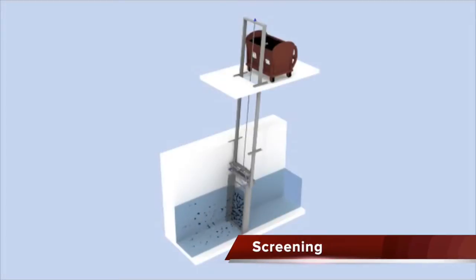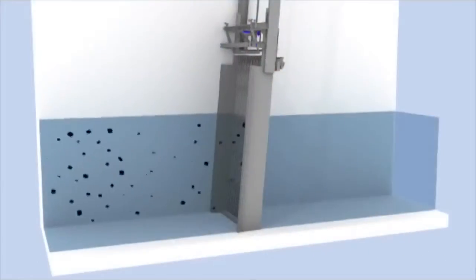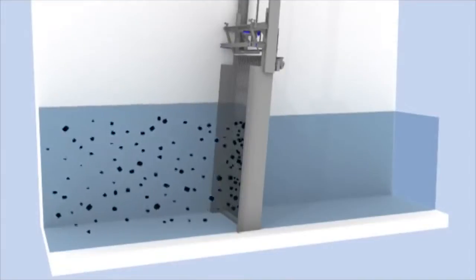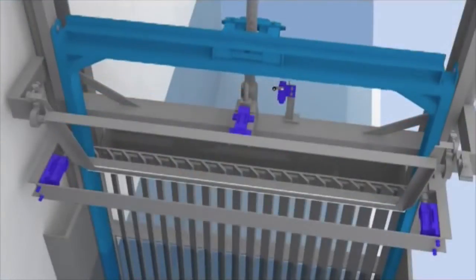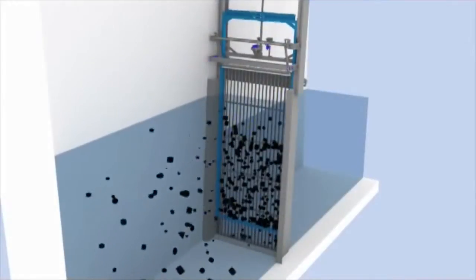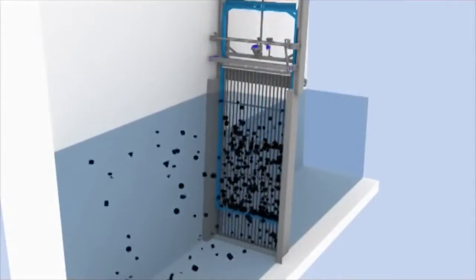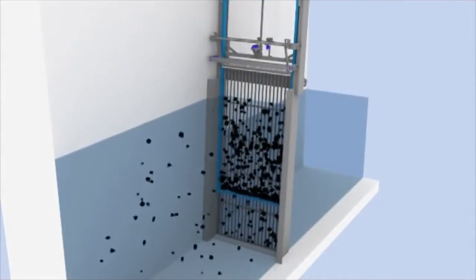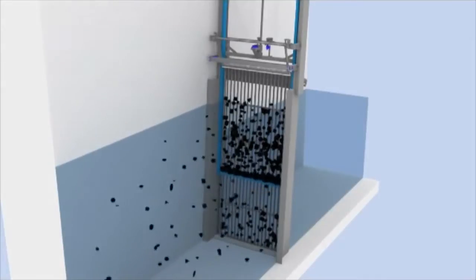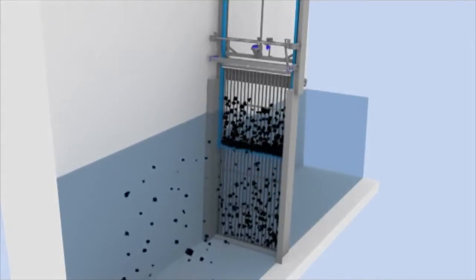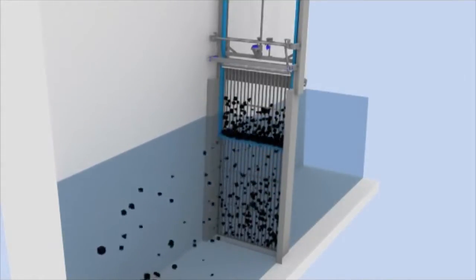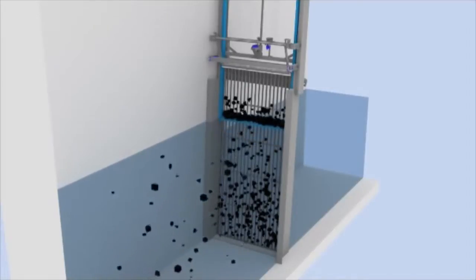Screening is the first and important station for both surface and wastewater. This process is to remove huge and suspended debris from the structure downstream, and to prevent obstruction in the plant. The screen opening size always affects the effectiveness of the screening process — for example, fine screening, medium screening, and coarse screening.